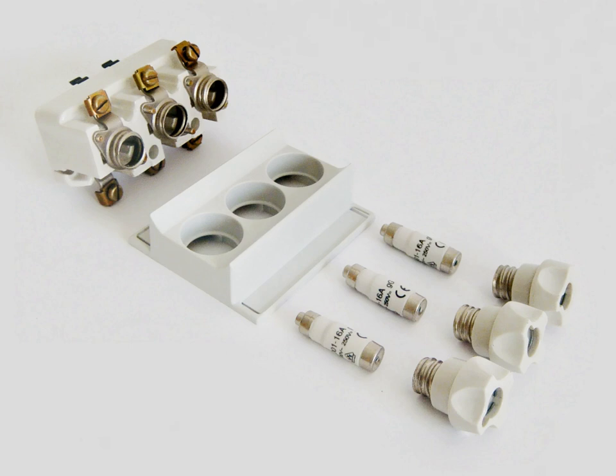The fixed part of the fuse holder contains a usually color-coded gauge ring, which will accept end caps up to a certain diameter. It is therefore not possible to fit a fuse of a higher rating than allowed for by the gauge ring. The size of the gauge ring is determined by the current rating of the circuit to be protected. Gauge rings are intended to be changed only by authorized personnel.